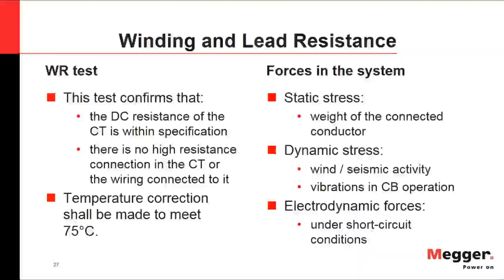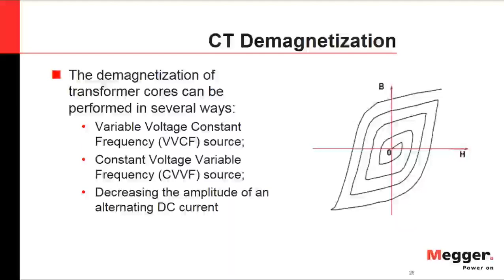After the winding resistance test of a current transformer, we must provide a demagnetization procedure. There are three methods: a variable voltage constant frequency source, a constant voltage variable frequency source, and a decreasing amplitude alternating DC signal. For a CT, applying an AC stepdown from the secondary side is easiest, since the secondary is designed for low voltage. For a power transformer, reaching saturation would require very high voltage, making demagnetization far more complex.